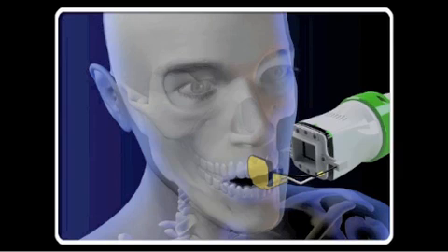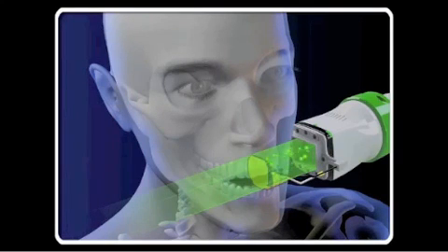TruAlign acts like the scope on a rifle. The beam is only 2% larger than the receptor. By drastically reducing scatter radiation and collimating the beam, the images, regardless of machine or receptor type, are clearer and crisper and contain greater information as shown here in this side-by-side comparison.